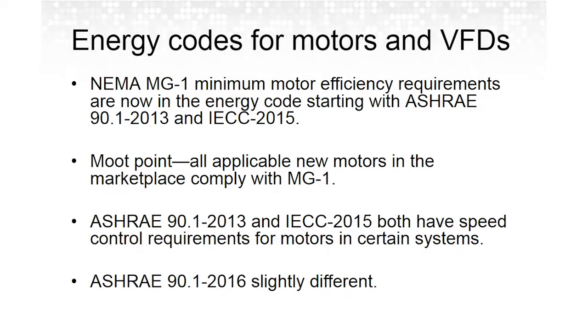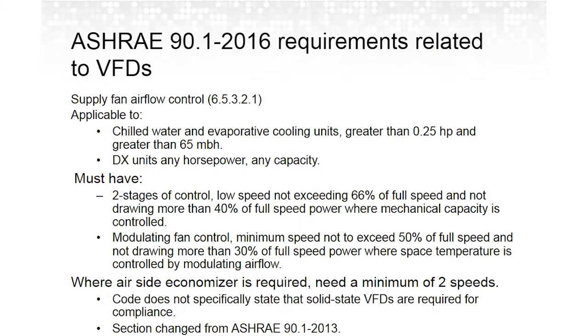It isn't mandated on a state level, it's mandated on a federal level. What is more appropriate to us as specifying engineers is that the applicable energy conservation codes have requirements for multi-speed operation under certain requirements. And 90.1 2016, the most current version, tweaked those a little bit, but they are more or less the same. Moving up to the left side, let's be upfront about this. Nowhere in 90.1 or IECC does it say that use of a VFD is mandatory. There's no prescriptive requirements. Rather, what we're seeing is a requirement for multi-speed control, which is more or less outlined here, and there's a little bit more.